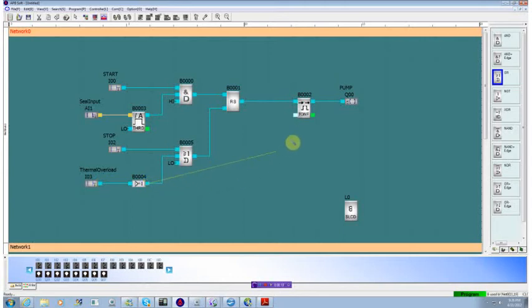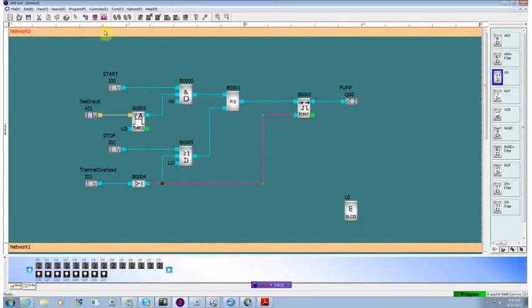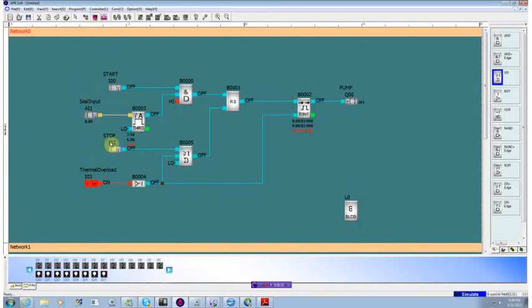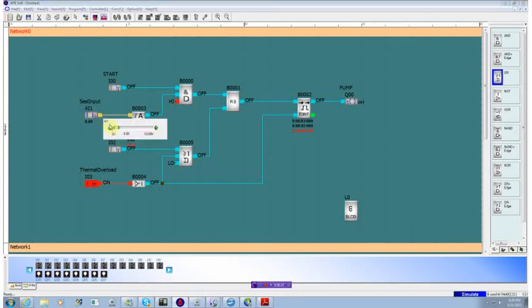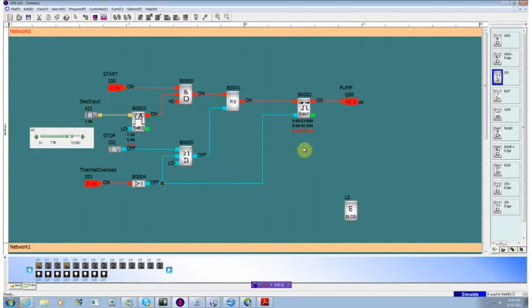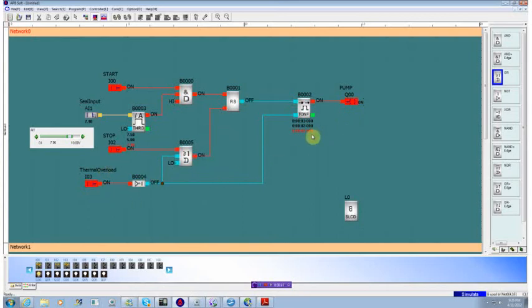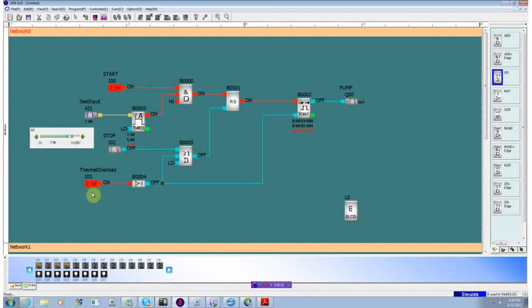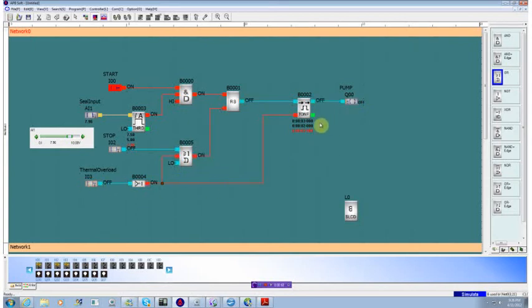So we'll take this output here, tie it into this, restart our simulator, disable the thermal overload, set our threshold, start our pump. We see that the pump starts running. If we hit our stop, it times down, turns off our pump. But if we hit our thermal overload, it immediately turns off our pump.